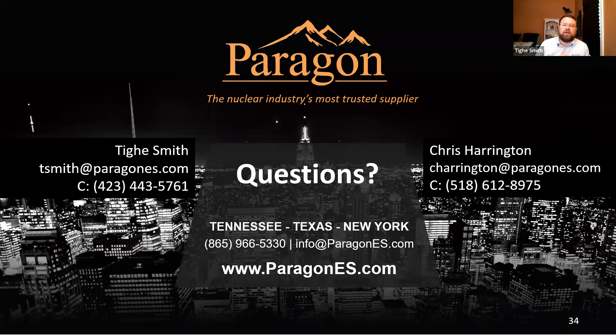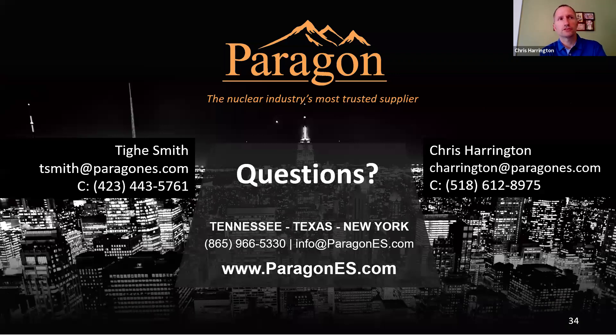What types of qualification tests do your repairs undergo before they're installed back in the field? Most repair and refurbishment activities involve a technical evaluation for equivalency in regards to fit, function, and qualification. Sometimes when replacing items of particular sensitivity for qualification — like relays, switches, or some electromechanical component — we'll have the subcomponent go through seismic testing or radiation testing or evaluation prior to installing it and post-assembly. In our equivalency evaluations, we cover what the original component was, what the new one is, how the parameters line up, and if there are any differences in form, fit, function, temperature ratings, or any of the common parameters.